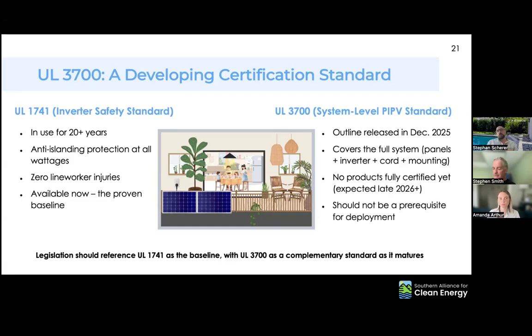I alluded to the fact that we're not getting rid of UL 1741. UL 3700 is a standard draft that was first published on December 11th, 2025. It was then released for certification this January. We, as many other companies, are already working on this. UL 3700 at this point is not a fully developed standard yet. While we can already get certified, it will still change, and it'll probably take 5 to 6 years before we have the fully developed UL 3700 standard.